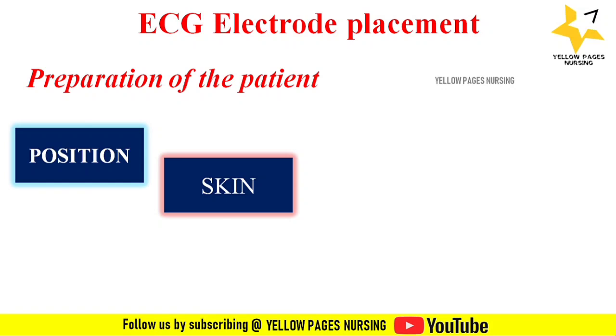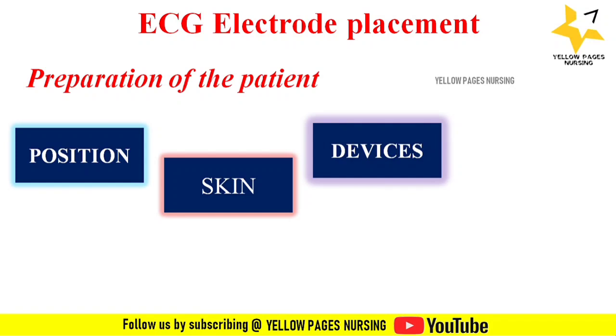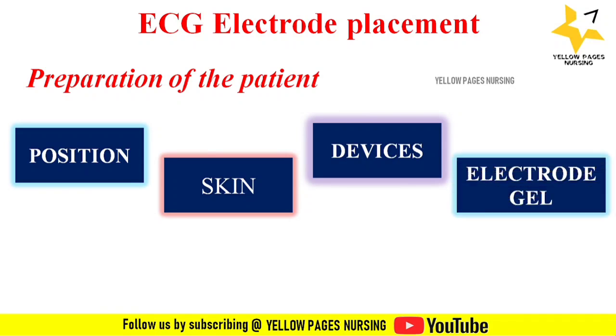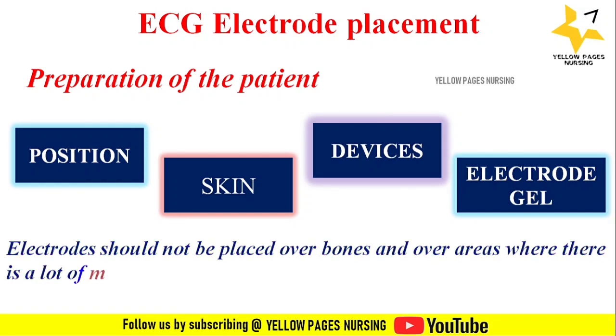Electrical devices such as mobile phones should be kept away from the patient as they may interfere with the machine and cause changes in the ECG reading. Electrode gel should be moist, as it acts as a coupling between the electrodes and skin to aid transmission of electrical activity. Electrodes should not be placed over bones or over areas with a lot of muscle movement, as this may create unwanted electrical activity.